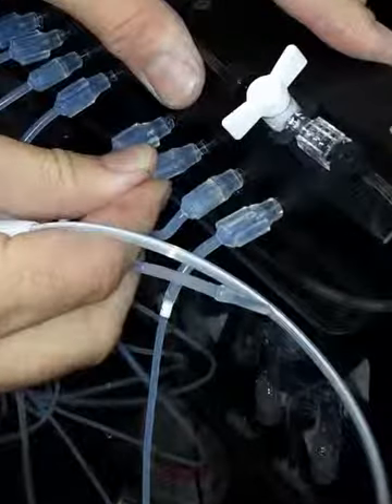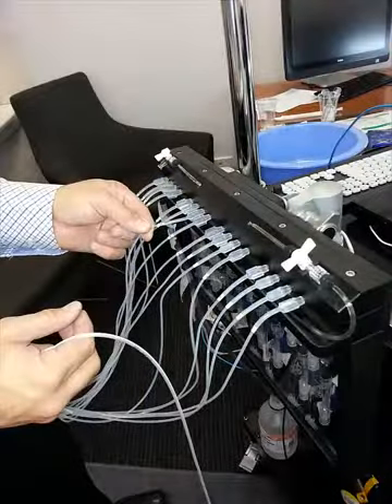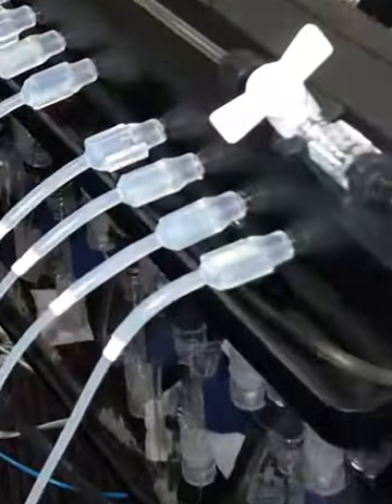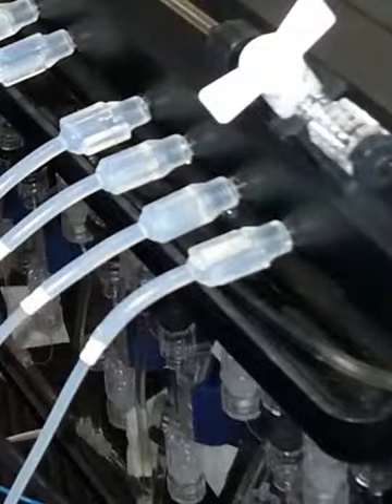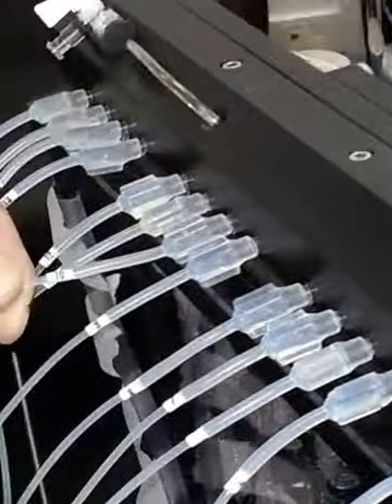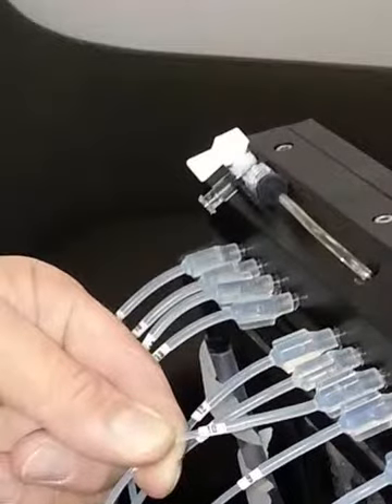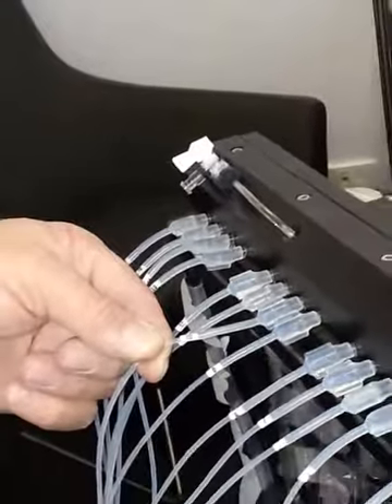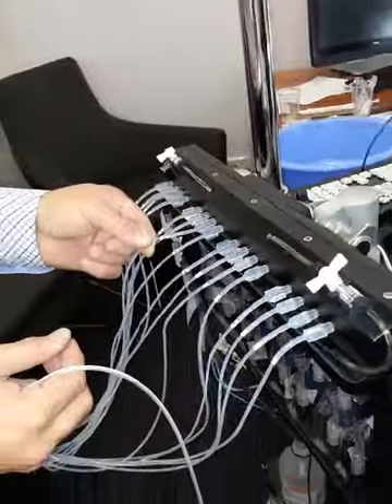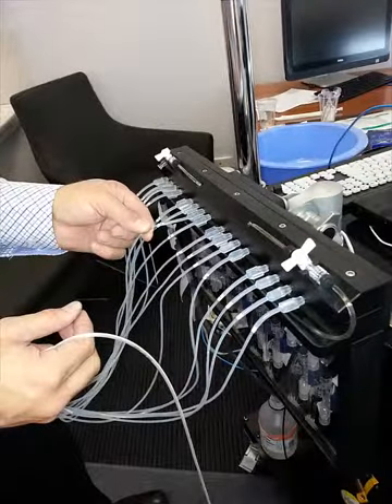Ensure that all of the connectors are firmly seated and that the numbering of the catheter channels is correct. You should be able to go from channel 1 at the right-hand end across to channel 16 at the left-hand end. Note that the channels of the catheter are in the opposite order to the recording channels. This is because the catheter is numbered with the most distal channel as number 1, whereas the recording software numbers the most proximal channel, number 1.